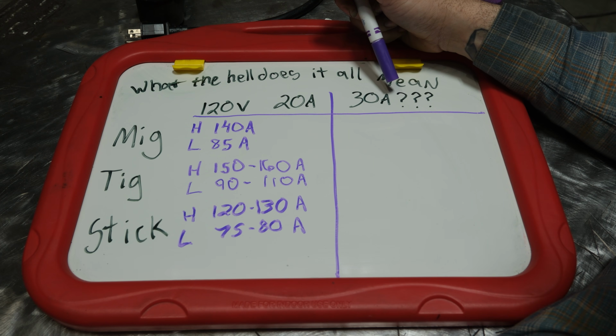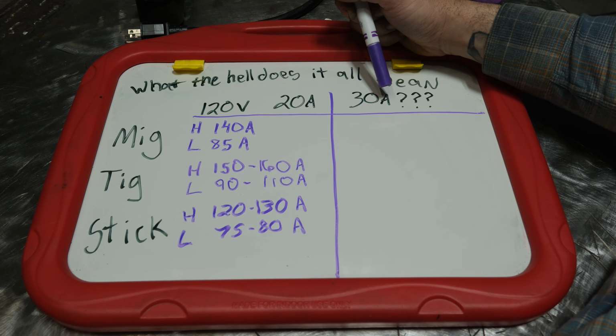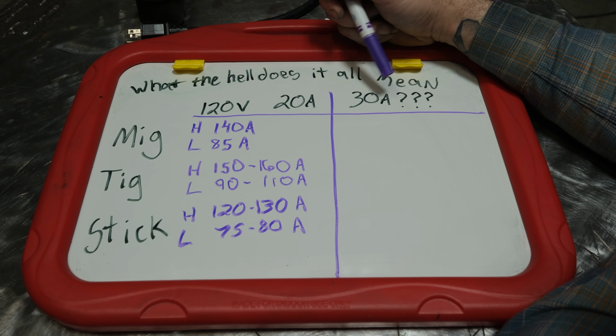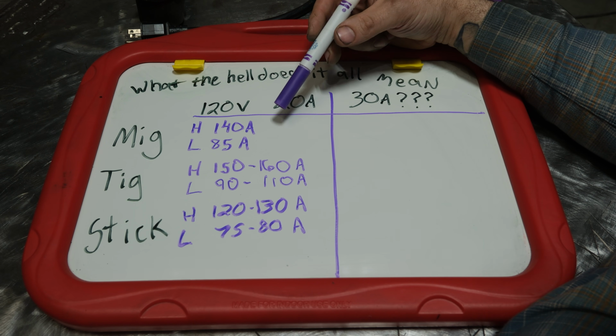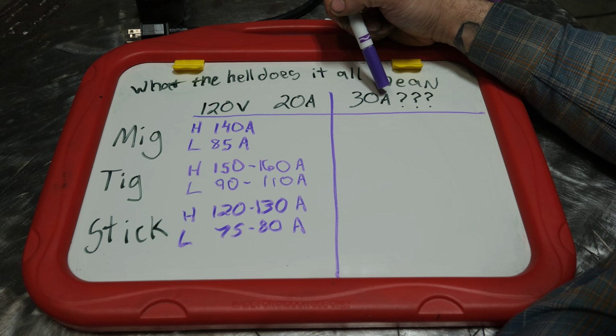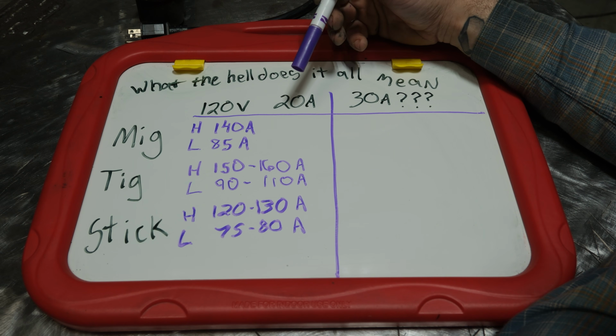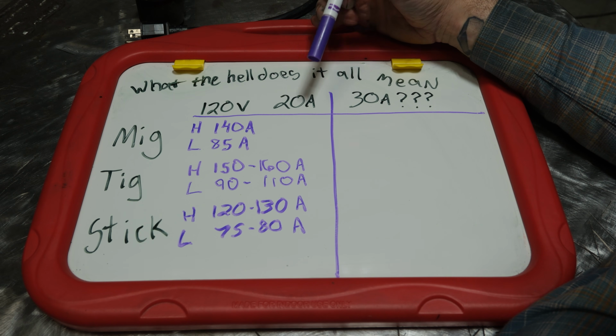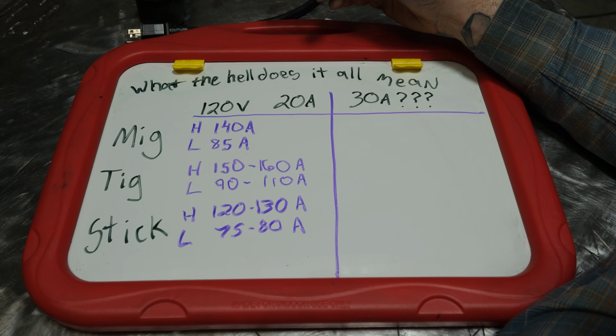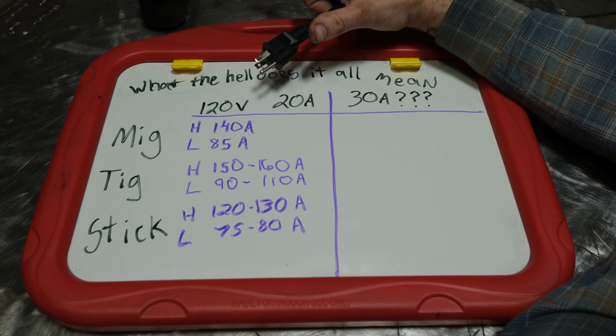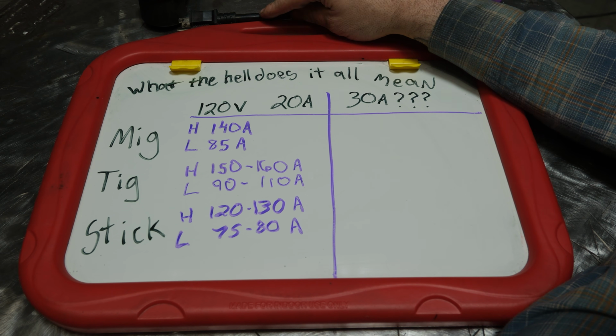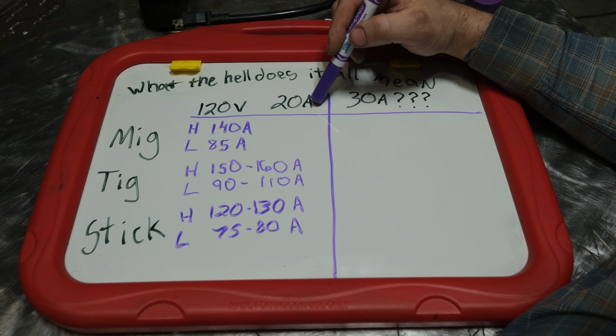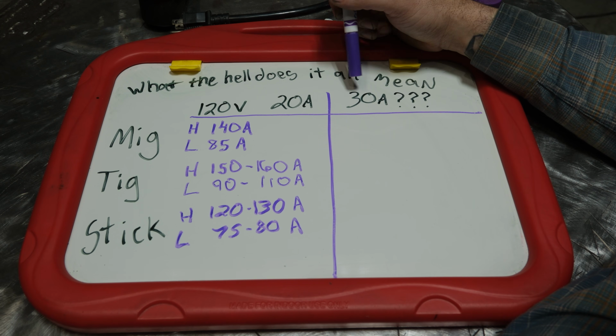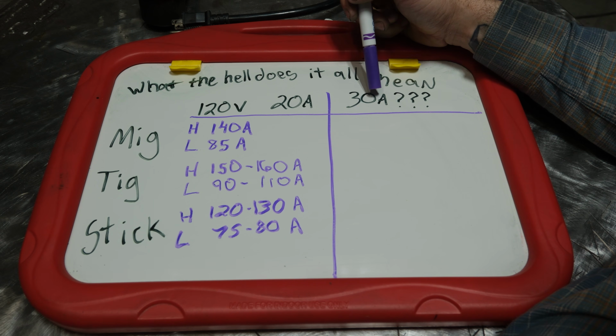Now, the next question you're probably wondering: well, if these are what I can get on a 20 amp breaker, why not a 30 amp? Well, here's the problem with that. A 30 amp breaker is not what any of these welders are designed around, because if they were, they would just constantly trip your breakers, and that's not good. You don't want that. And I think at that point they would have to have a different plug on them, the 30 amp plug, which looks nothing like this 20 or the 15 that I showed you earlier. So that becomes an issue of safety.